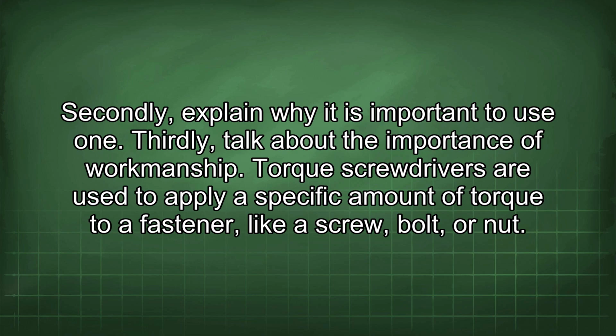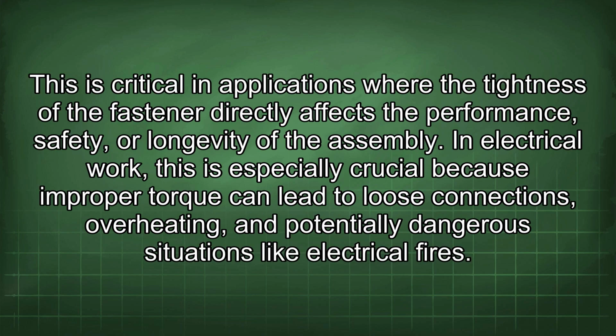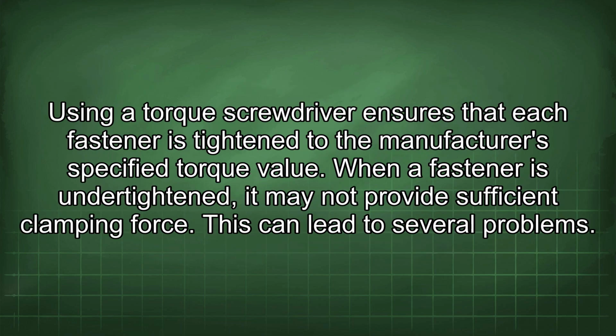Torque screwdrivers are used to apply a specific amount of torque to a fastener, like a screw, bolt, or nut. This is critical in applications where the tightness of the fastener directly affects the performance, safety, or longevity of the assembly. In electrical work, this is especially crucial because improper torque can lead to loose connections, overheating, and potentially dangerous situations like electrical fires. Using a torque screwdriver ensures that each fastener is tightened to the manufacturer's specified torque value.